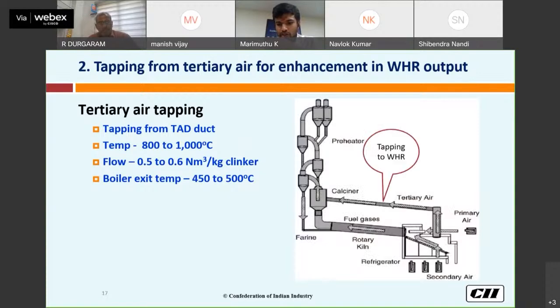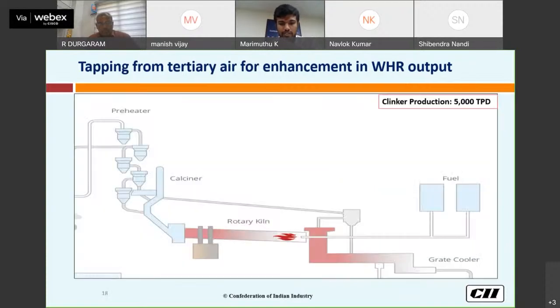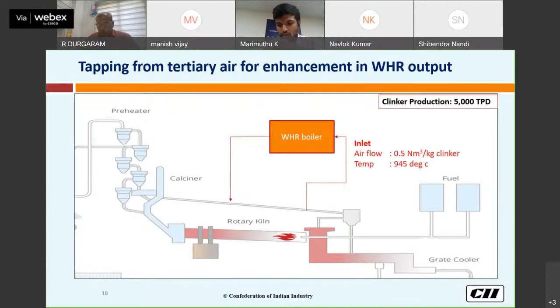So this is the normal circuit. This is the area for tapping up WHR, between the clinker cooler hood and the calciner, where the tapping is taken. This is the circuit for the WHR boiler. The inlet condition airflow is around 0.5 Nm per kg at a temperature of 945 degrees, and in the outlet condition the airflow is the same and the temperature is 460. So this is the drop in the WHR, and the output we get is around 4.1 megawatt.